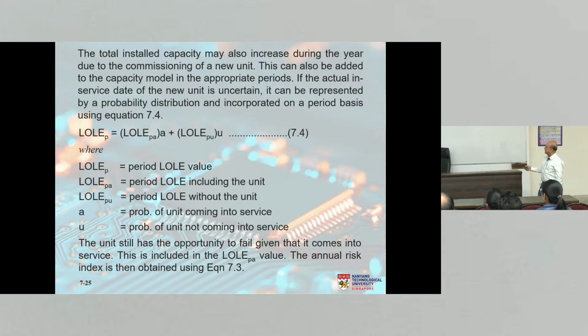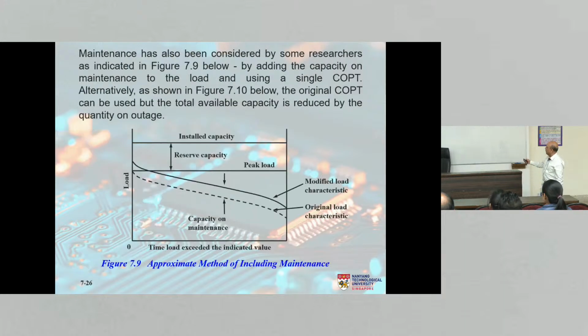The approximate way is this. Let's go here first. So the approximate method of including maintenance is this: whenever some generator is on maintenance, I assume that the load profile is now going up by the capacity of the generator on maintenance. So for example, the generator on maintenance is 40 megawatt. The original load profile is the dotted line. Now I'm going to add 40 megawatts to the load profile, and I'm going to shift the load profile completely by 40 megawatt. Why? It is equivalent to the load going up by 40 megawatt, is it not?